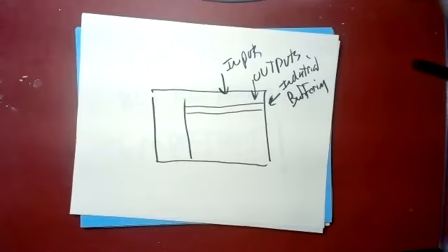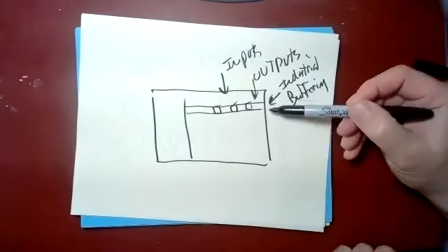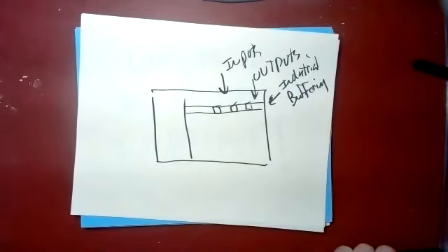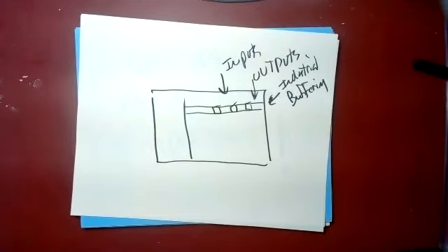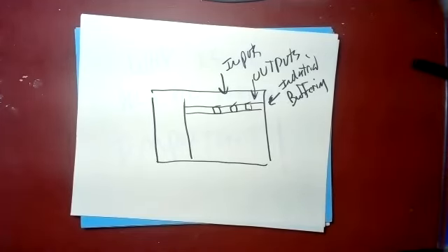It is isolated. In electrical terms, we call that isolation, generally using something called optical isolation. That means they use special chips in this buffering layer that physically disconnect the internal wiring of the PLC from the external wiring of the real world, all those switches and motors and all things that can go shock you out in the real world.